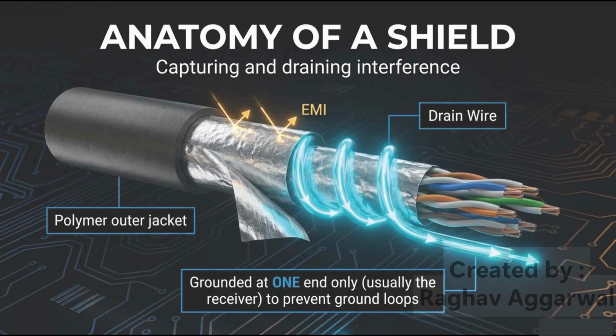Let us see how a shielded cable works. The outer polymer jacket provides physical protection for the cable. Beneath that, the shield surrounds the signal conductors. When electromagnetic interference reaches the cable, the shield captures much of that unwanted energy. A drain wire then provides a path for the interference to be directed away. An important point highlighted here is that the shield is grounded at only one end, usually at the receiving end. This practice helps prevent what are known as ground loops. We will revisit this concept in detail later.